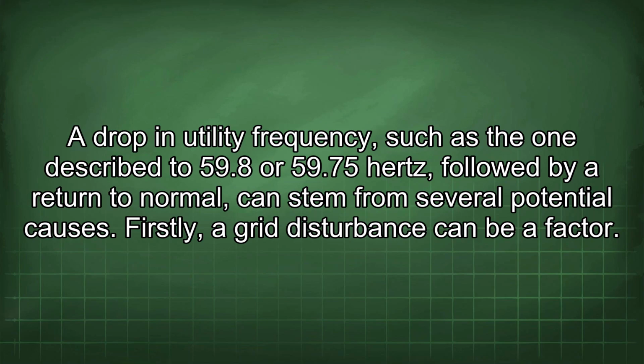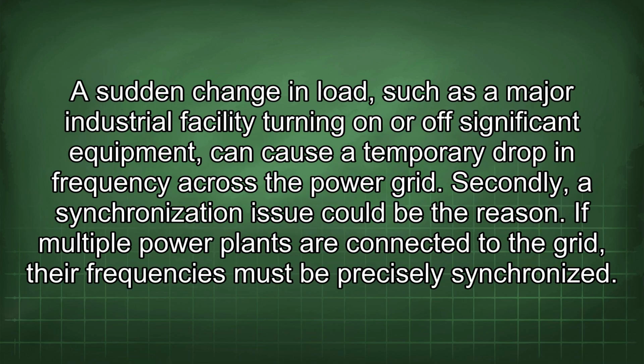A drop in utility frequency such as the one described to 59.8 or 59.75 Hz, followed by a return to normal, can stem from several potential causes. Firstly, a grid disturbance can be a factor. A sudden change in load, such as a major industrial facility turning on or off significant equipment, can cause a temporary drop in frequency across the power grid.